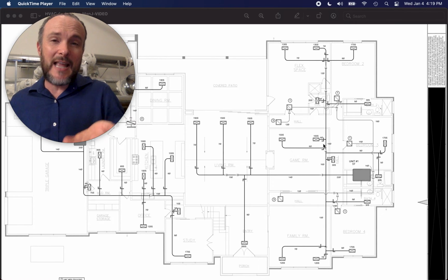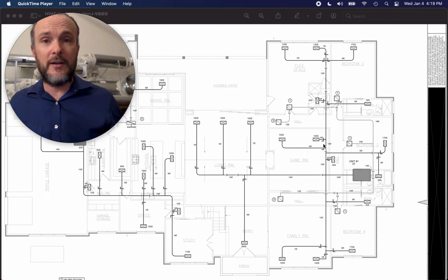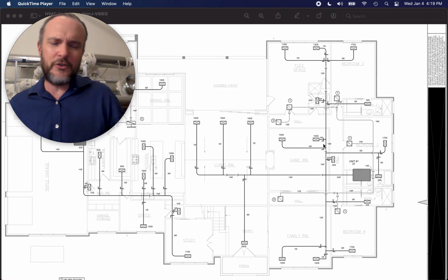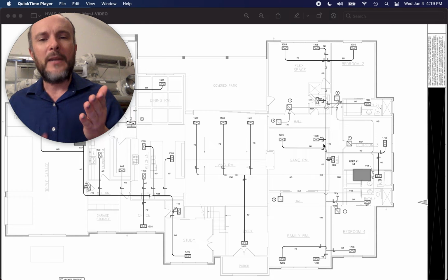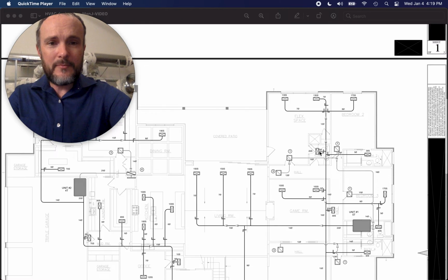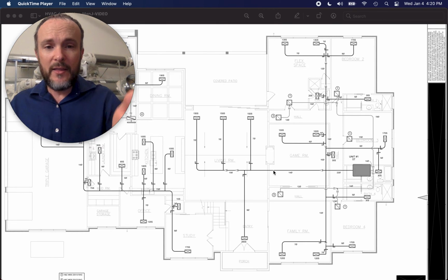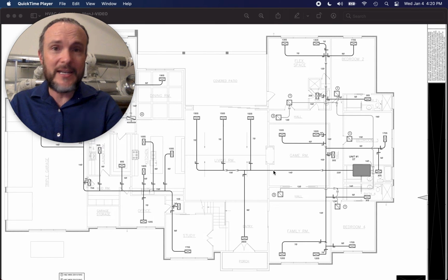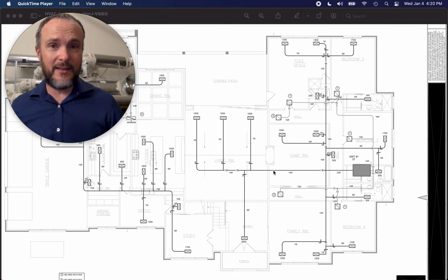And even if it's a slab on grade, we don't really count it in Manual J software unless the perimeter is exposed to outside. So the fact that it's just sitting on dirt doesn't really hurt the room at all. This game room, for example, has no exposure to outside. All the walls face interior space. The ceiling of this entire house is under a conditioned attic, so there is no ceiling exposure in this room either.